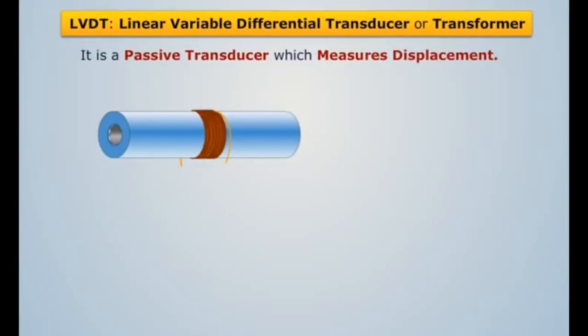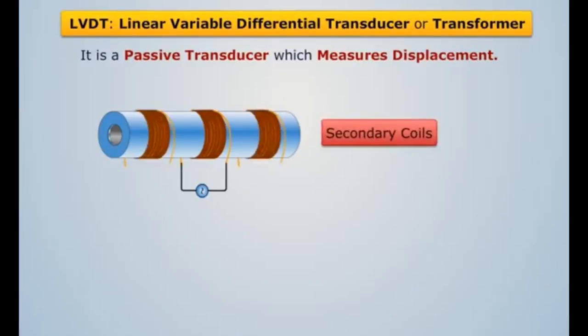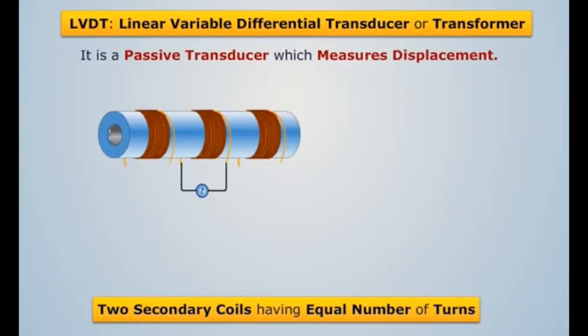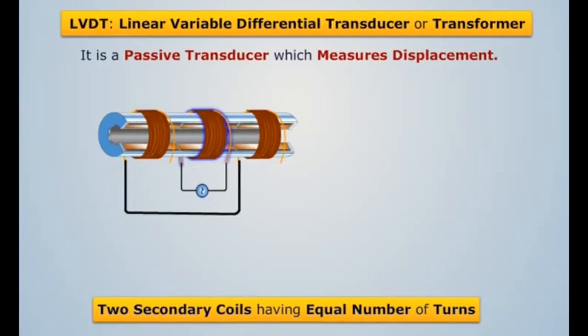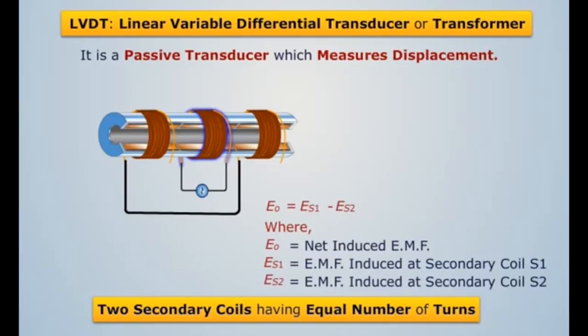It consists of a primary coil bounded on a hollow cylindrical rod and is connected to an AC source. It also consists of two secondary coils having equal number of turns and is bounded on a hollow cylinder at equal distance on either side of the primary coil. The two secondary coils are connected with each other in series opposition. We see that a movable soft iron core is placed inside a hollow cylinder. The position of this core with respect to the two secondary coils will affect the magnetic coupling between the primary and two secondary coils. Let's now understand how this LVDT works.